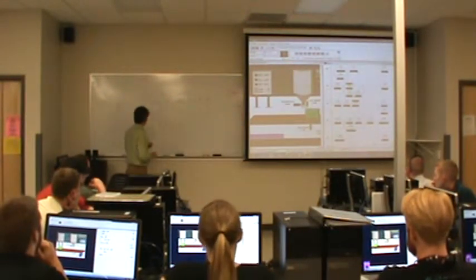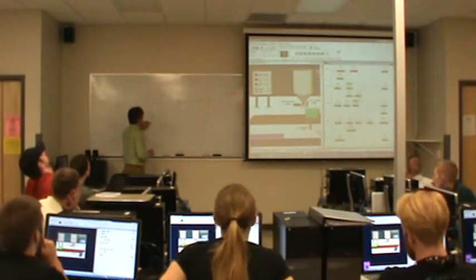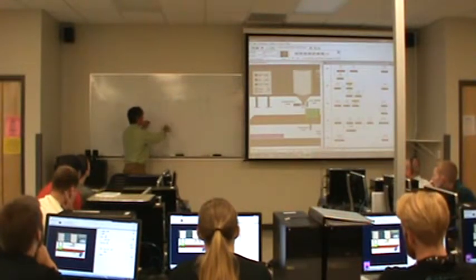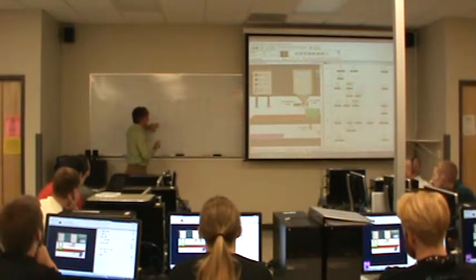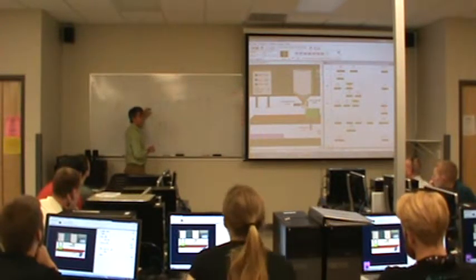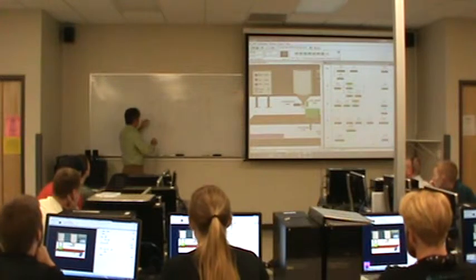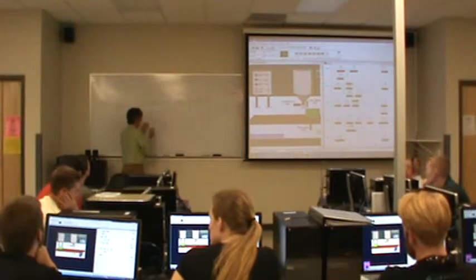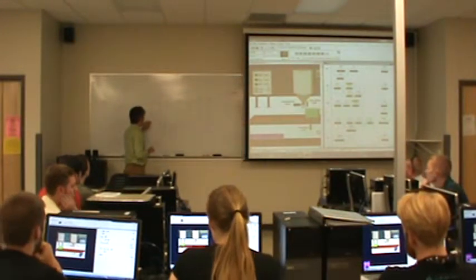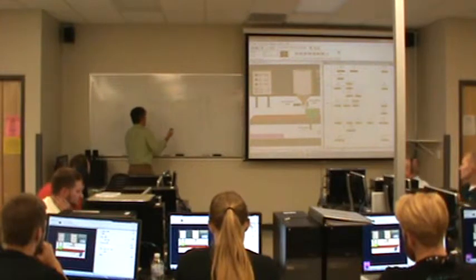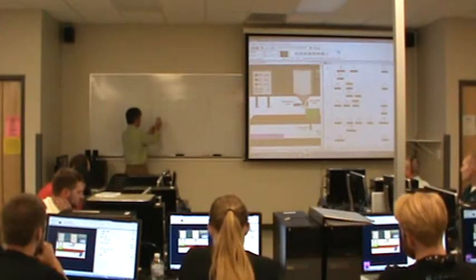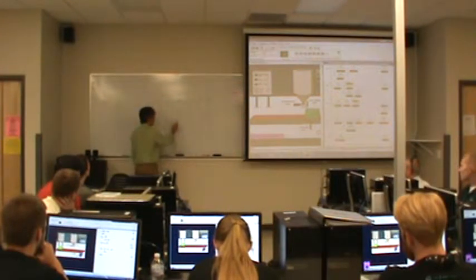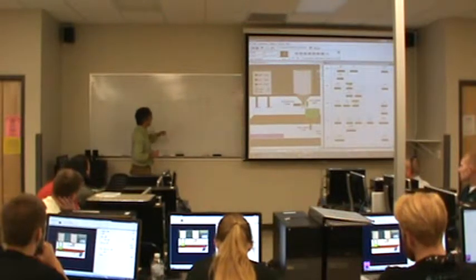Okay. Now, let's continue. If the full bit is true, prox is not true, level is not true, this also will only occur for one scan, because any time prox is not true, this bit is going to be shut off, and we'll be back up here. Does that make sense? So we're not terribly worried about what happens here. We can essentially program based on prox and level, but we'll consider the fact that we've noted a full box. If we had a full box but prox is not true, it's time to bring another box into position. Right? So anytime there's not a box but there was a full one, we're going to forget that next scan, and it's time to get another box in place. So those would both be ones, and they look exactly like they did before.